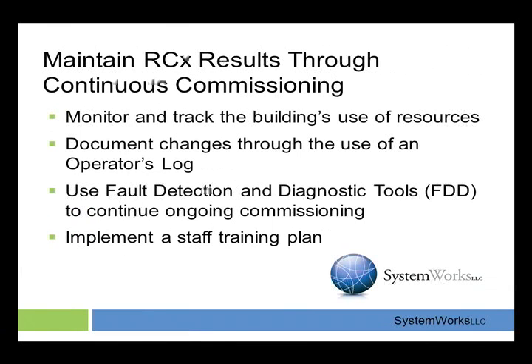This slide is continuous commissioning, how to maintain results, retrocommissioning results through continuous commissioning. And these are just a few examples of things that your building automation system can do, as well as your staff can do to maintain this. Because as everybody knows, if you make changes, you could be saving a lot of energy, but as years go by, if you don't continually look at the energy usage and the system to keep it optimized, things start to get out of whack and you would end up back to where you're not efficient anymore.